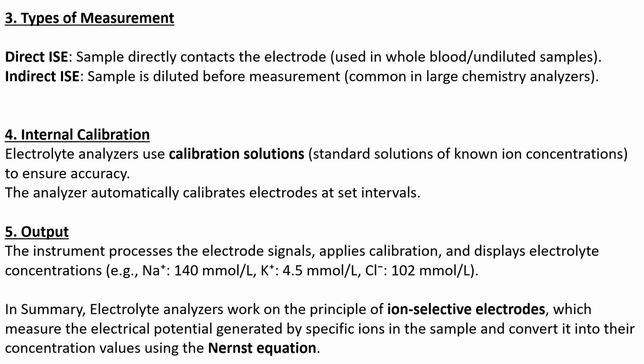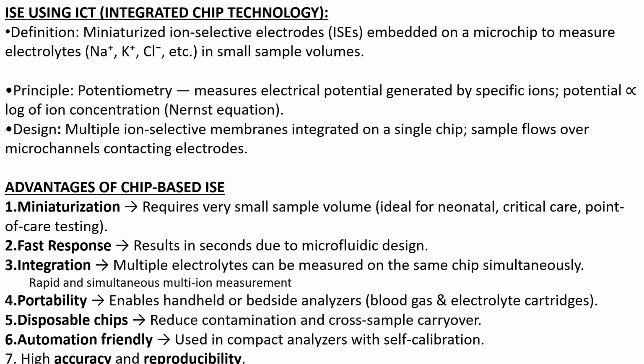In summary, electrolyte analyzers work on the principle of ion selective electrodes, which measure the electrical potential generated by specific ions in the samples and convert it into concentration values using the Nernst equation. The traditional ISE analyzers use bulky electrodes with special ion selective membranes. So instead of the same, a newer methodology is introduced, that is ISE using ICT or integrated chip technology.